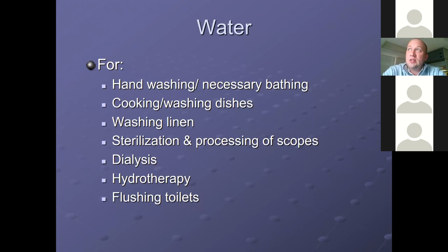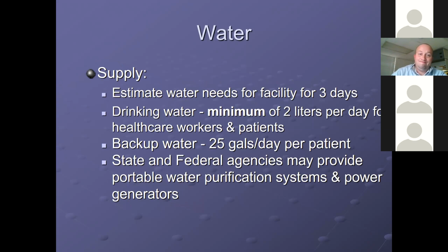So some of the issues we faced: dialysis. Some machines can run off of non-potable water, some can't. Understand if yours can. Suction. Like I said, if you don't have water pressure, your suction pumps can't run. Here is another thing that you can't do if you don't have water. And to be clear, this wasn't a boil water order for us, just we lost water pressure. We had to shut down all of our transfer and booster pumps, including our fire pumps.